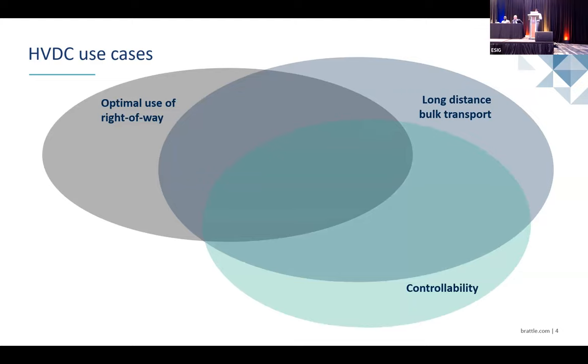And then, these converters are power electronics based. Therefore, you can precisely control. That means in a grid where you need full controllability, these HVDC converters will be really useful. And one more thing which you can't do with AC connections is asynchronous connections, where you have two asynchronous networks but still want to transfer power between them. Then you can use HVDC.